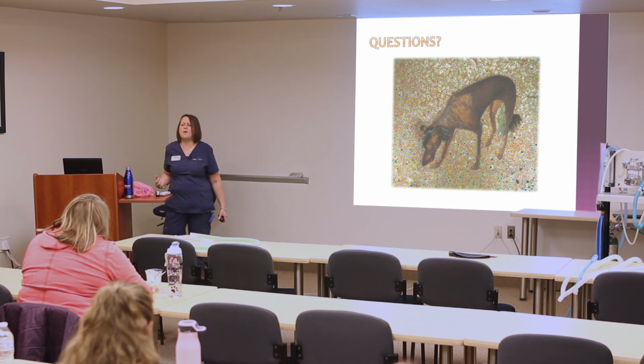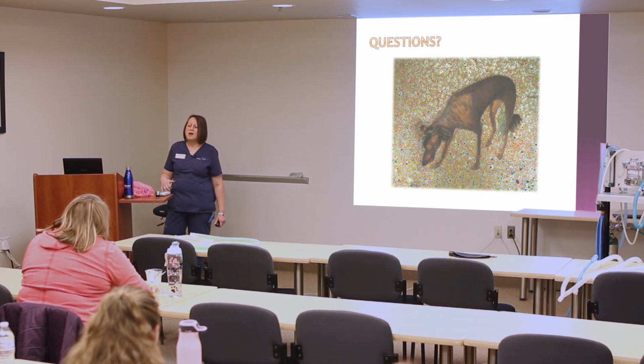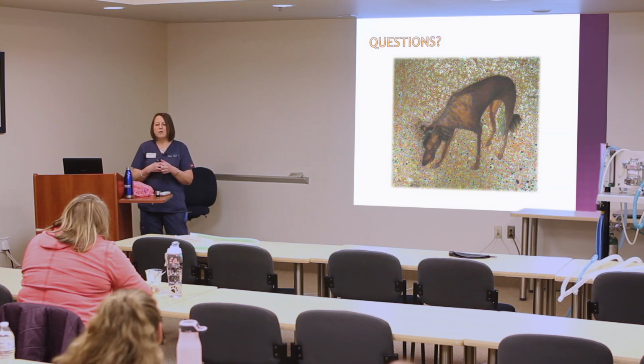Once it gets to a year, I just have an ethical problem, like it's a year old, maybe I should change it. But it's really going to be based on common sense and what is the size of your patient, how much carbon dioxide are they making, so how much burden is there on that carbon dioxide sorb to work. You'll see some of the machines are bigger, like the SodaSorb assembly on the Matrix machines, it can hold more SodaSorb than the EVAD machines. So theoretically, I should be able to use those machines for longer because they hold more volume of SodaSorb. So think about, how long are your procedures, what are the size of your animals, and that is going to ultimately determine how quickly you go through the SodaSorb. It's not just the straight hours thing, because you really have to put common sense into it, like I talked about earlier. So yeah, it could still be good.